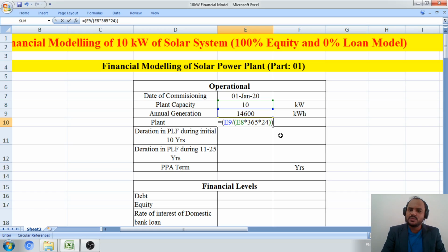So if this power plant is working 24/7, or 24 hours, it is going to feed electricity to the utility grid out of the overall 24 hours, after self consuming. The solar power plant has only a small window span in the day. Out of the 24 hours, the peak hours in which the solar power plant generates electricity and feeds it to the utility grid are 5 to 6 or 7 at max. So that is why the plant load factor for a solar power plant is lesser compared to the thermal power plant, the atomic power plant and any other power plant.